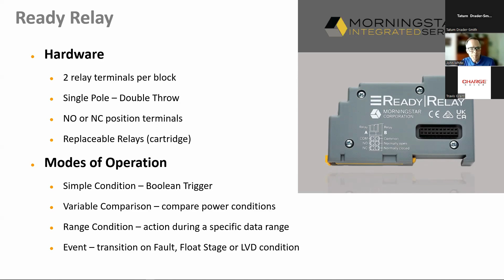Again, modes of operation, simple conditions, variables - you can set different ranges and/or events. This is one of the different pull-down menus that make life easy from a configuration standpoint. It's got 52 system values to choose from: common settings, battery settings, PV settings. It includes the shunt data and state of charge when you're trying to control the different devices. It looks at charge and load states, and it has a conditional logic of and/or.